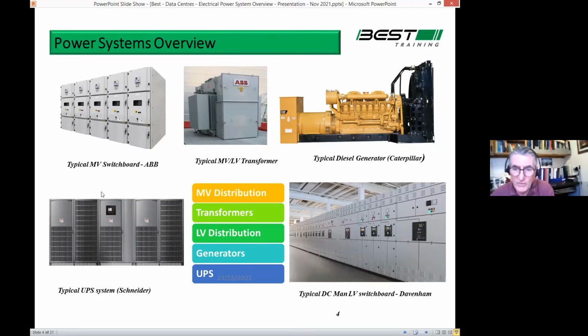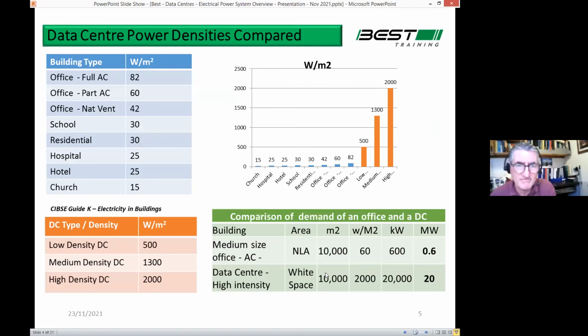And then the low voltage distribution system. So you can see that board, that's a typical data center board. You can see the length of that. That's probably 30 meters long, that board. And probably £500,000 worth of switchgear in that. So that's the type of thing. As someone quoted once to me, power in a data center does not come cheap. It certainly doesn't. So that's what we're going to be talking about anyway.